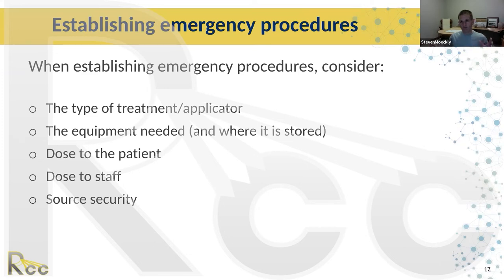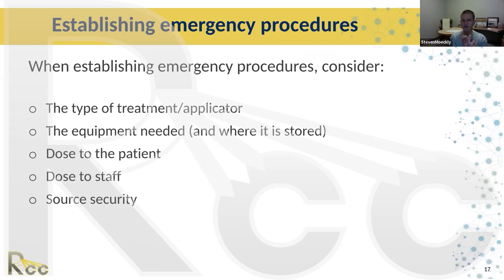Remember, it's the patient getting the bulk of the dose. If I enter the room as a physicist and I'm a meter away from that patient, I can be in there for an hour before reaching my yearly dose limit. It's really not a staff problem — it's a patient problem in terms of dose. Source security is also critical: if the source is out and in the pig, how are you going to secure that room? Are you going to post somebody until a service engineer arrives, and if so, has that person been trained?